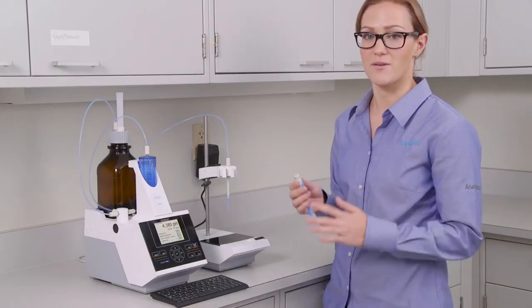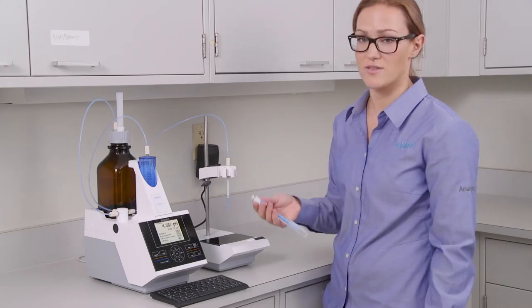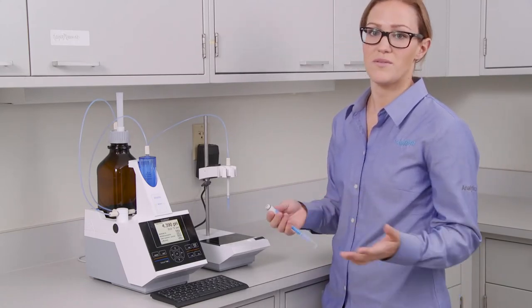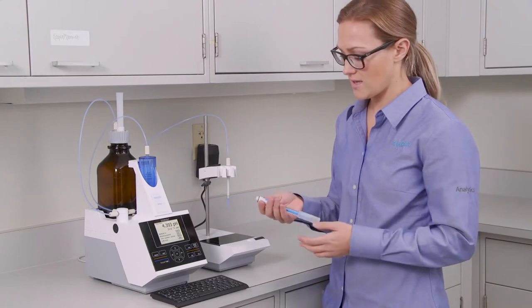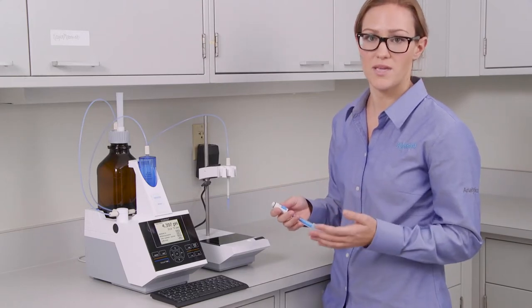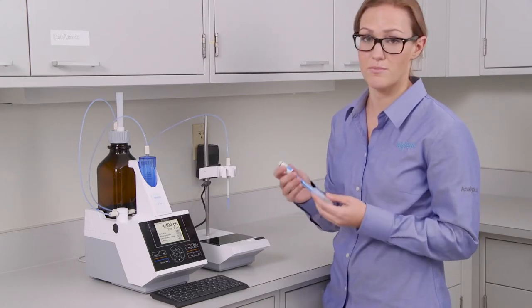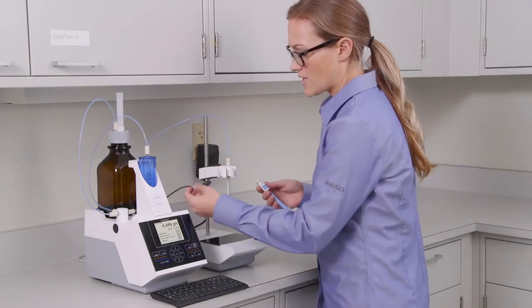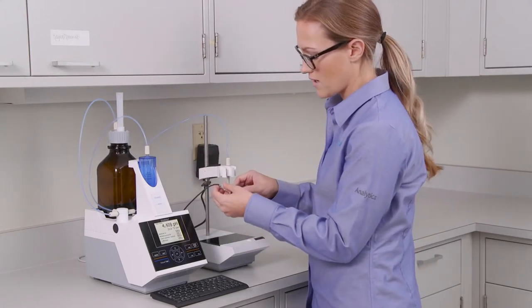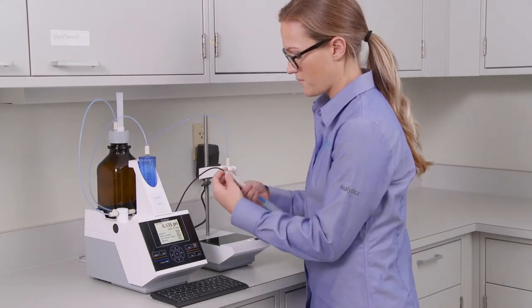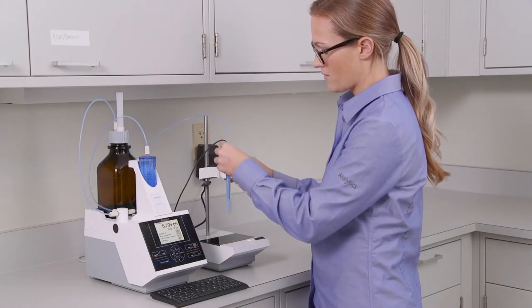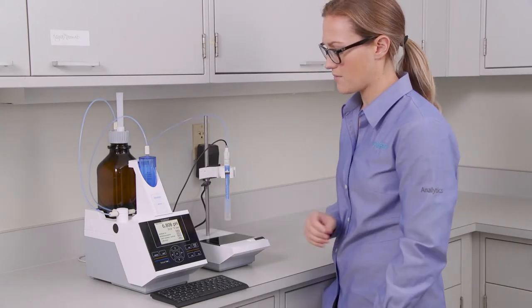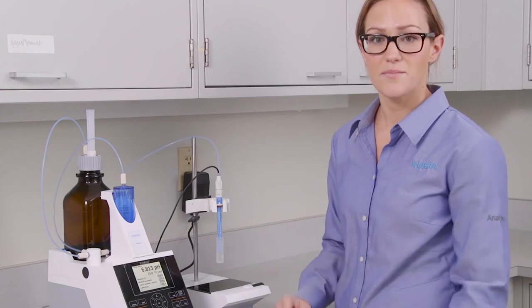The final step to getting your complete titrator set up is your electrode. You may be using a number of electrodes. In this case we're just going to be working with a simple pH combination electrode. This is our blue line 11. You'll take the other end of your electrode cable and just connect it to the top of your probe. You'll take your probe and put it on top of the clamp like so. And it's as simple as that.